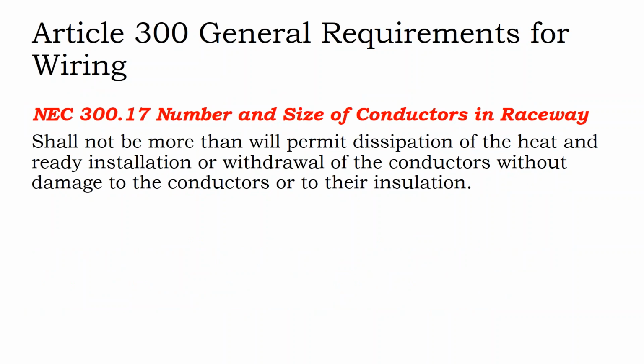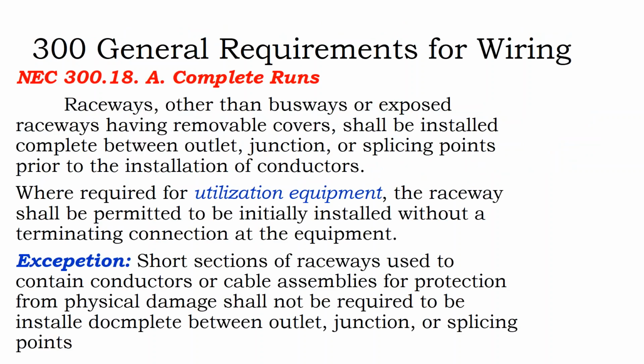The number and sizing of conductors in a raceway shall not be more than what will permit the dissipation of heat and be able to install or withdraw a conductor without damaging other conductors or their insulation. That might be wishful thinking. Usually when you're pulling a conductor out, you can, but it can also get stuck and hung up on the other cables inside. So often you have to pull everything out and put everything back in. And that assumes your conduit remains intact, as it might not in a direct burial run when you have the weight of the earth pressing down on it.